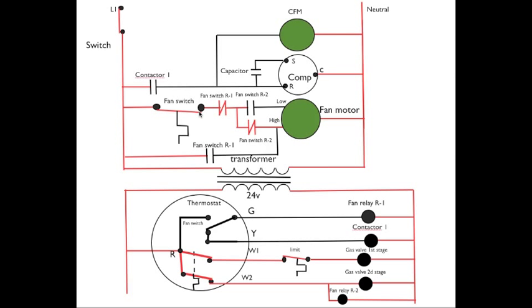So up in the high voltage, the power comes through the closed fan switch, through the normally closed R1 fan switch. Fan switch R2 has reversed position, so it's no longer passing power to low and it passes power down through the closed contacts to energize the high speed of the fan motor. So in that way we have made the fan go to the high speed of the fan motor go to high speed in a second stage gas heat.